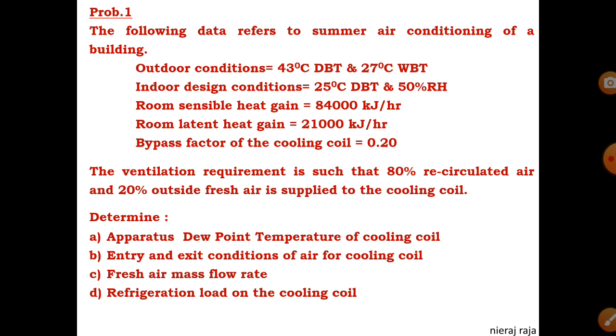The ventilation requirement is such that 80% recirculated air and 20% outside fresh air is supplied to the cooling coil in order to get the required indoor condition. Out of the total air supplied to the cooling plant or cooling coil, 20% should be outside ambient air at 43°C DBT and 27°C WBT, and 80% should be recirculated air coming from that particular room.